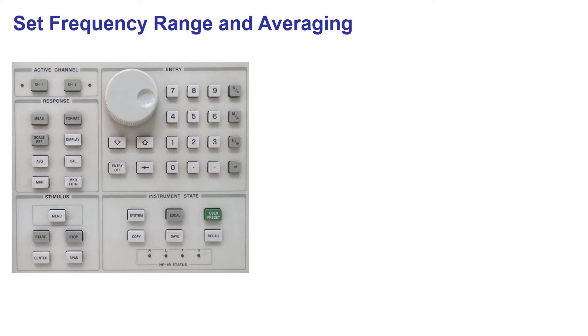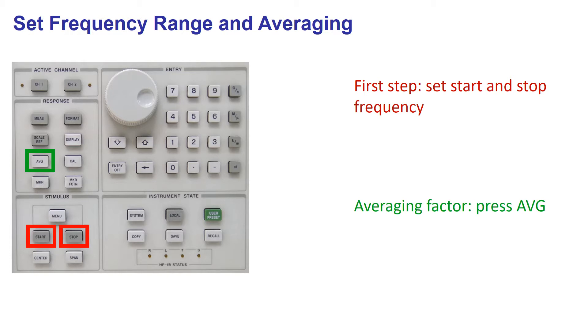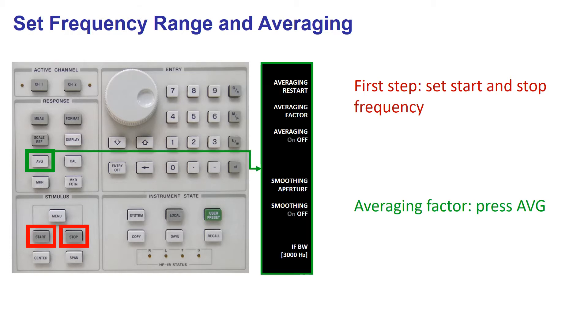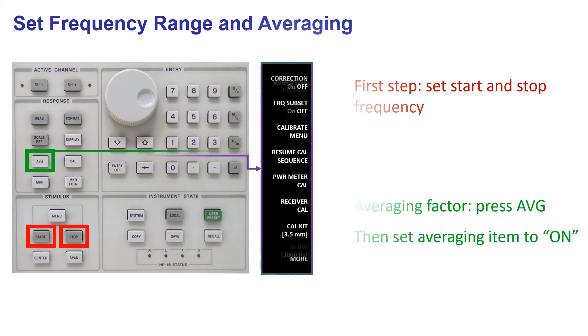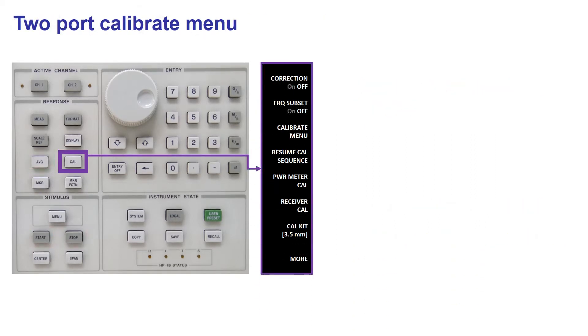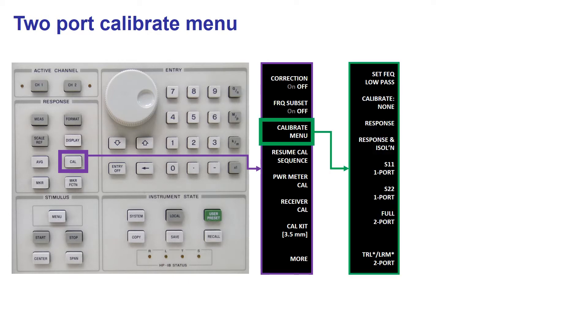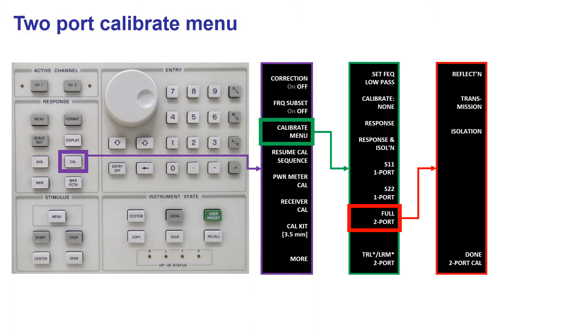Again, you need to specify first the frequency range and set the averaging. You press the averaging key and switch the averaging to ON. Then we press the calibration button again and choose Calibrate menu. Now you must specify full two-port and a menu is shown displaying the labels for the three main parts of the calibration procedure.